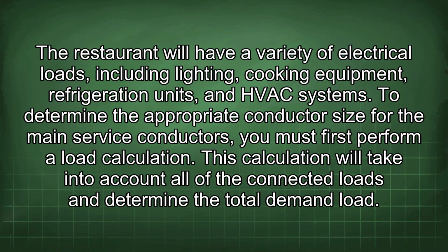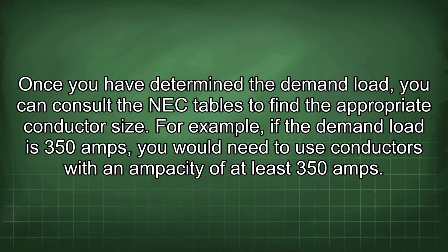The restaurant will have a variety of electrical loads, including lighting, cooking equipment, refrigeration units, and HVAC systems. To determine the appropriate conductor size for the main service conductors, you must first perform a load calculation. This calculation will take into account all of the connected loads and determine the total demand load. Once you have determined the demand load, you can consult the NEC tables to find the appropriate conductor size.